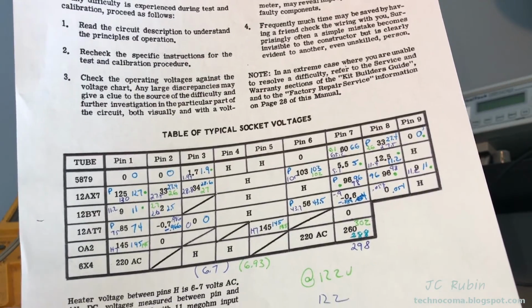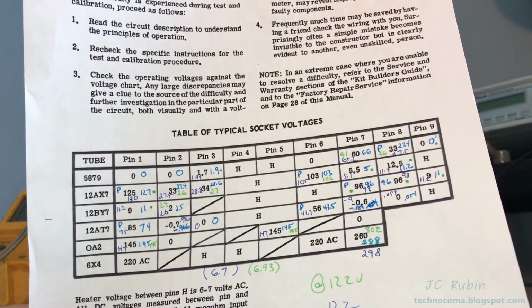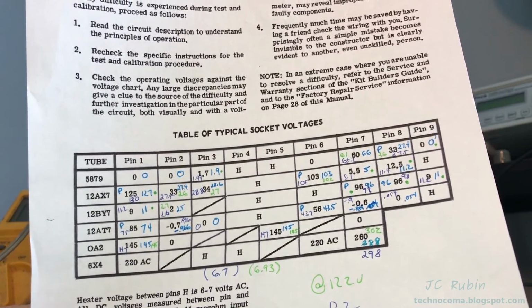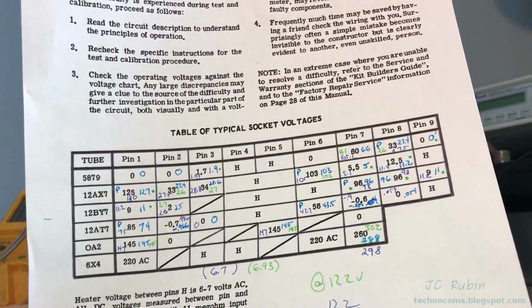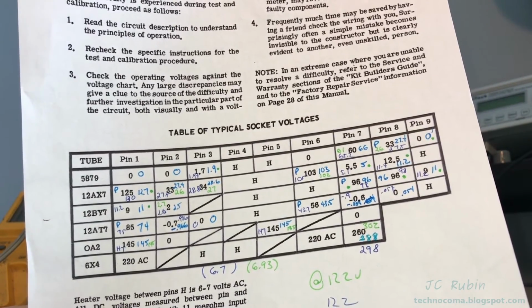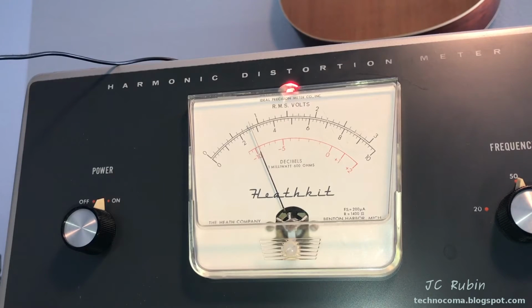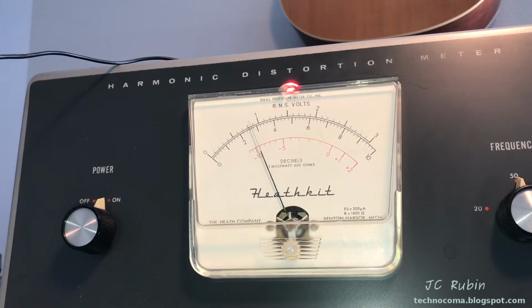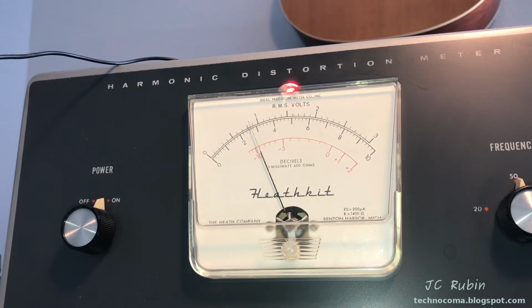Was it like amazing, crippling pull down of DC on this unit? No, but was it appreciable? Yes, it was. So it's a good thing that that capacitor was removed and replaced. And just to demonstrate the effect that today's work has had on this unit, we're looking at the pilot lamp plugged in again to the input for the voltmeter calibration. And we know that the voltage is 6.91 as it was just recently calibrated. We're on the 10 volt setting, and we could see that it is now sitting over there.